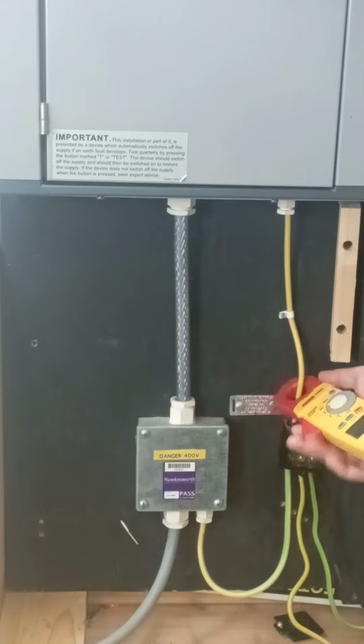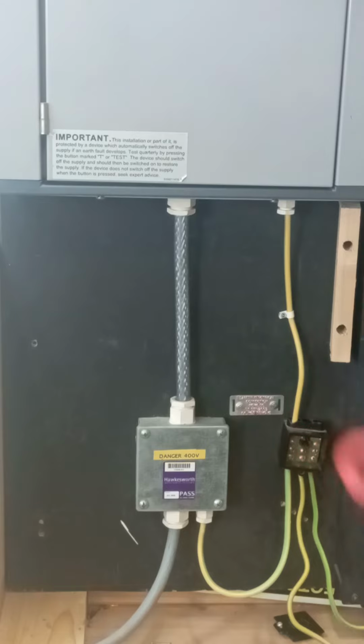1.65 milliamps flowing there. The reason we've got 1.65 milliamps flowing there is I've got a photocell and a wee electronic driver controlling one of my lights. Obviously, the more electronic equipment that we have, the more leakage current that we're going to have travelling down that protective conductor. Remember, more than 10 milliamps is considered high protective conductor current.